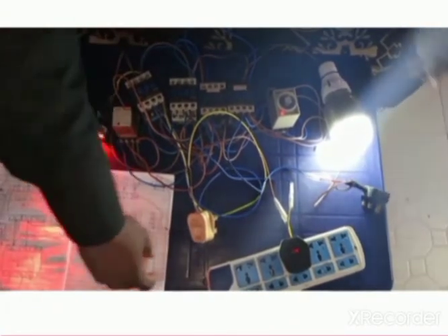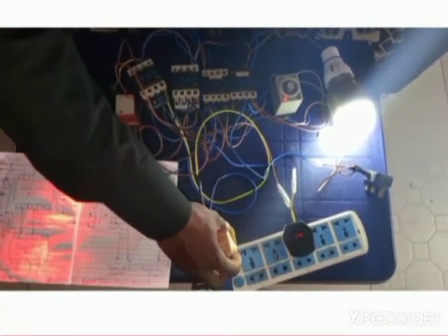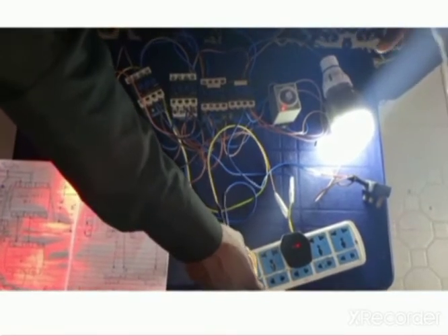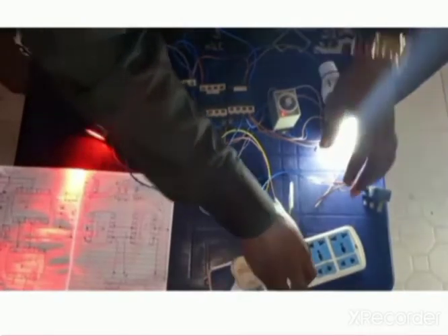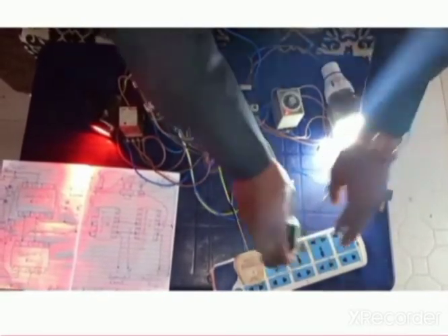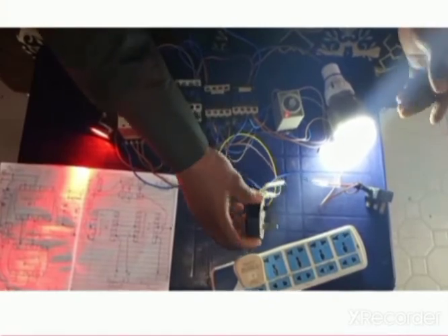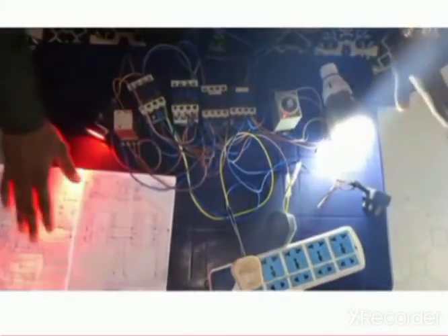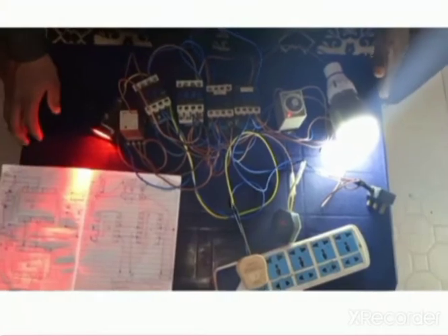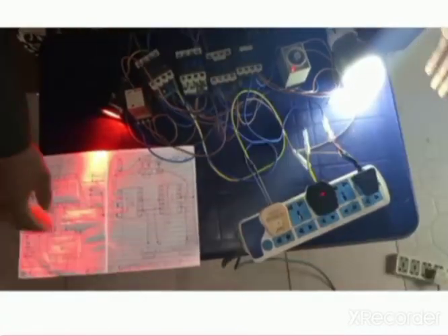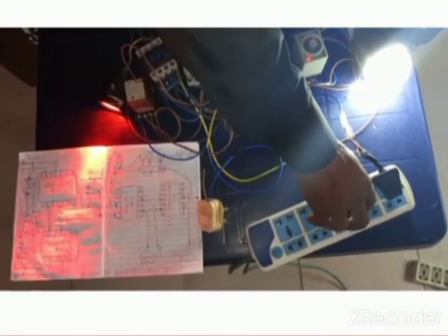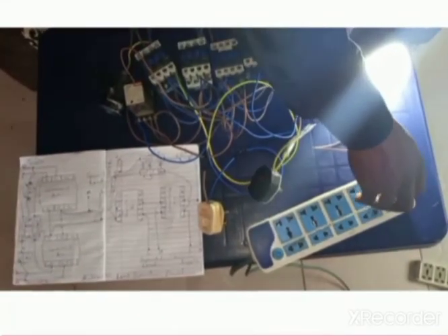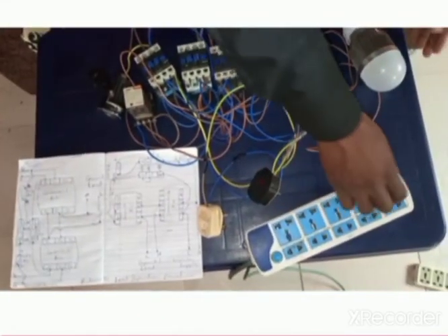Looking at it very well, you see that when the utility comes, the utility has to take over from the generator and supply both the separated load and the general load, just like this. It has supplied both loads, and there's no supply at the generator side, showing that both loads are now on because the utility is powering both of them. If the utility goes, it will return to the generator, just like this. And when there is no generator, it will return to the inverter, just like this. And when there is no inverter, the whole supply will go.